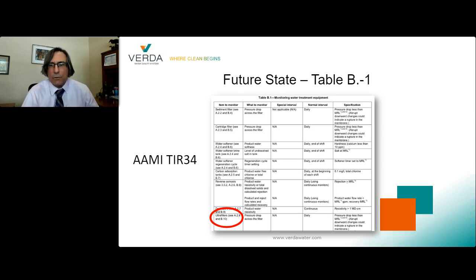The water testing is only to confirm that water treatment equipment and processes are working as designed and expected. However, based on your frequency of water testing, you could have something go wrong and not be aware of it for weeks. While some problems can be seen, like staining, high bacteria readings in critical water can't be seen. This could present a problem for items only requiring high-level disinfection or for instruments that are difficult to sterilize due to their design. You have tests to validate processes and results, but they are generally confirming efficacy based on statistics. Statistics does not mean you don't have a problem. It just means there's a high probability you don't have a problem.